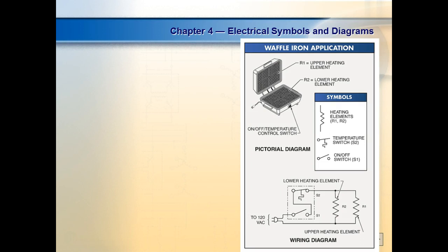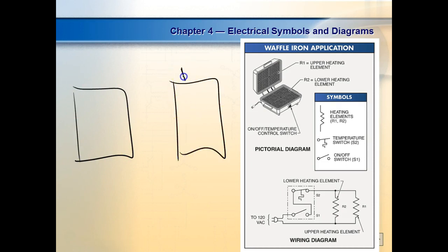Now in control circuits, we usually have 2 sections. We have what we call the control circuit, and this is going to be low voltage. And then we're going to have a power circuit. So the control circuit is going to control the power, right, you understand? So this will be control, this is very common, and that'll be power. Your control is going to be at a low voltage, ours is going to be considered 220. And then over on your power side, this will probably be a high voltage. So your power circuit is usually really isolated, this is the one that's going to be inside these cabinets. It's going to have locks, tags, and all that kind of stuff because that's got a voltage high enough to kill you, right, you understand?